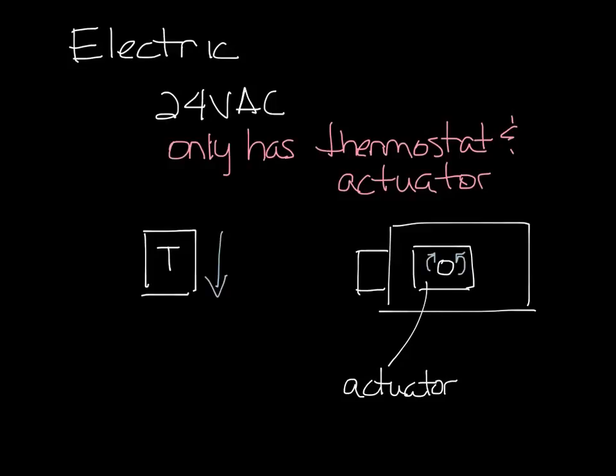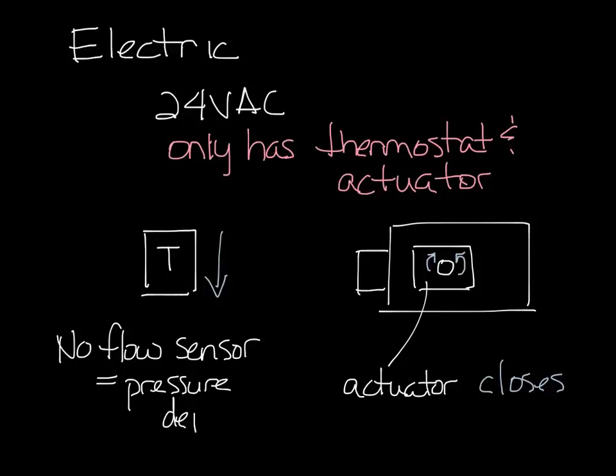So when the thermostat senses a reduction in temperature, it drives the actuator closed. There is no flow sensor in an electric VAV box. So an electric VAV box system is pressure dependent. This means that changes in system pressure will change the amount of air flow you get out of your box. Because of this reason, electric systems are likely to have large room temperature variations and they're not used very often.